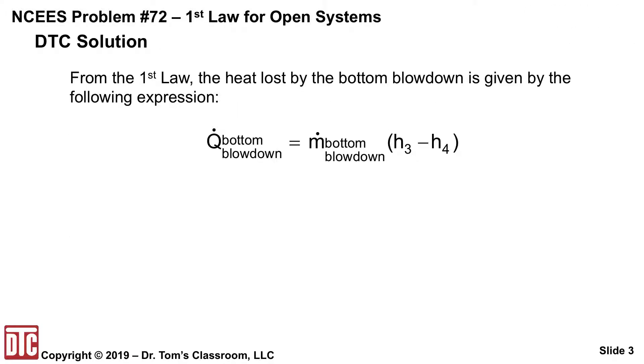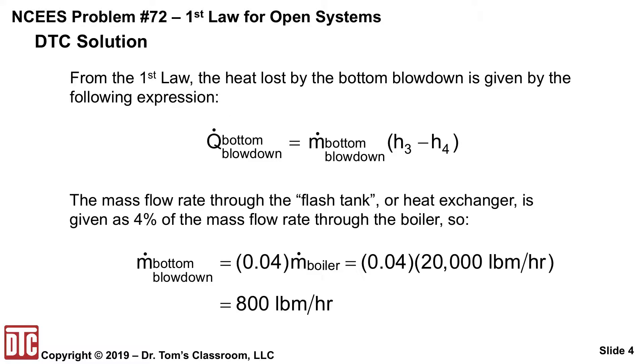From the first law, the heat loss by the bottom blowdown is given by: Q-dot equals M-dot times the difference in enthalpies, H3 minus H4. The mass flow rate through the flash tank or heat exchanger is given as 4% of the mass flow rate through the boiler. So taking 4% of the 20,000 pounds per hour gives 800 pounds per hour for the M-dot bottom blowdown.